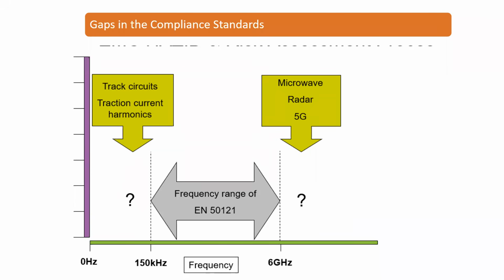That's one thing, but for equipment we need EMC testing in an EMC test lab to check whether any electromagnetic noise is generated above the specified limit. To minimize it, we do electronic circuit design to reduce electromagnetic radiation, and second, proper installation practices.